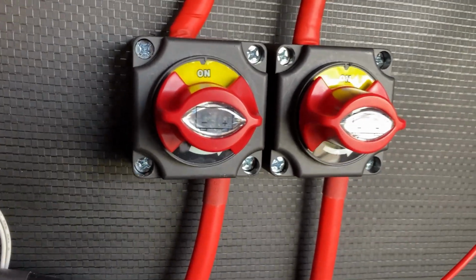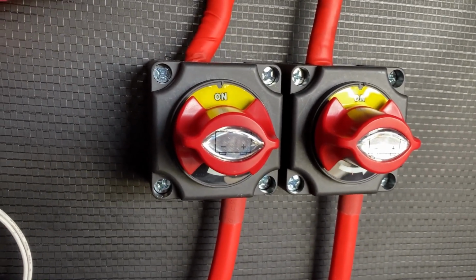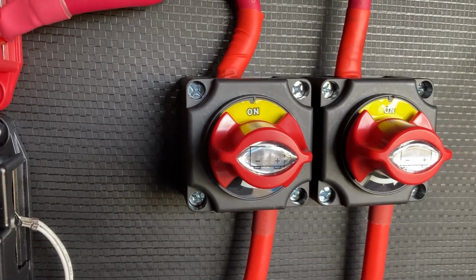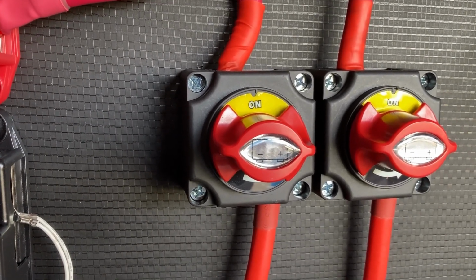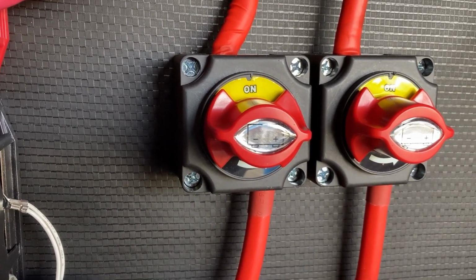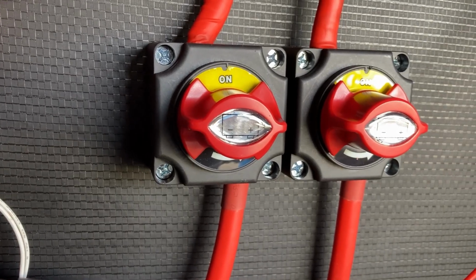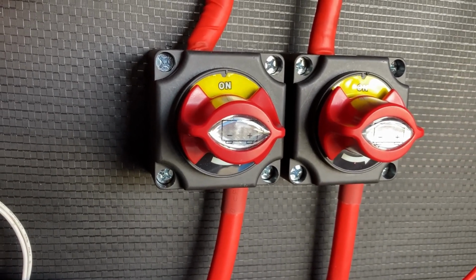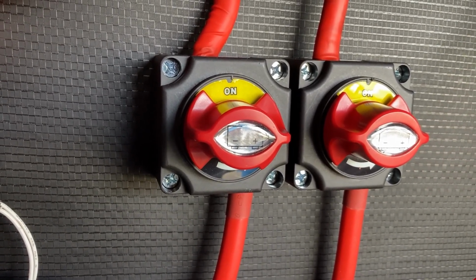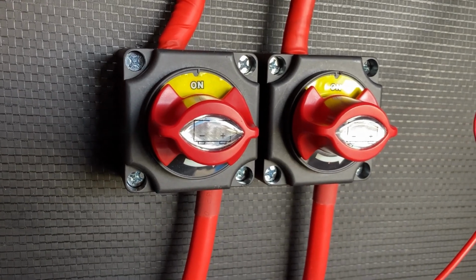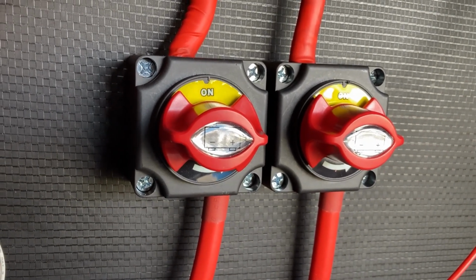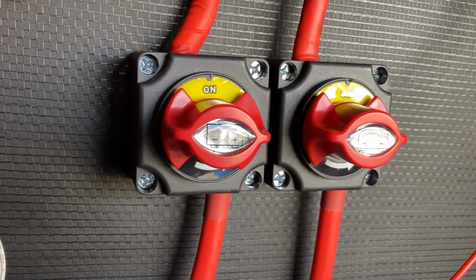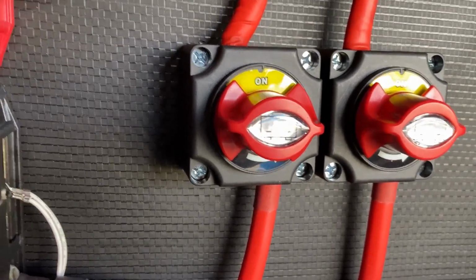They're pretty stout switches, rated at 300 amps each. So the overkill on these components is way above anything these batteries will be discharging at. The fuses on the positive leads of the batteries are 125 amp fuses, so they'll blow if too much power gets pulled out of the batteries, or there's a short circuit. All the safety is built in here.